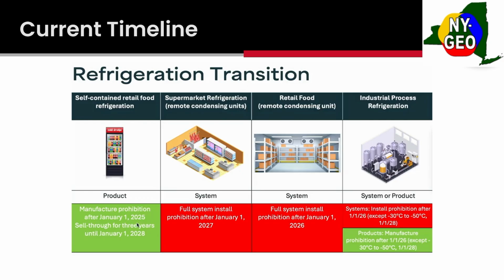So you look at the self-contained retail food, manufacturing stopped in January. They do have a 3-year sell-through date. Full systems, this is probably where if there's any regulatory change, it's going to impact full systems for supermarkets. They have until 2027. Units or systems with remote condensing units, they have until the end of this year. So again, if you look at that timeline, there's no way there could be any changes made to that. And then same thing with industrial refrigeration. They have until the end of this year to get systems installed. So there's no way, if there are any rule changes, that it would affect this equipment.